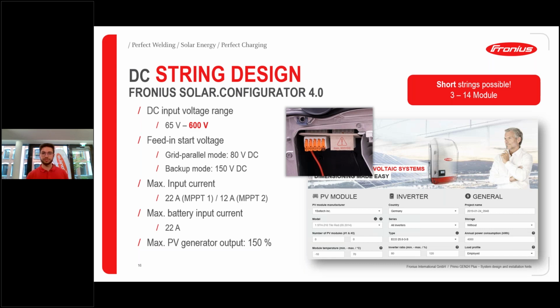And there is also a difference if we have a backup mode now. And in the backup mode, of course, there is no grid supplying us. So we need a little bit higher voltage to also supply the inverter itself with power. And therefore we start at 150 volts on the DC side. So there is a difference between grid parallel and backup mode when it comes to the feed-in start voltage.